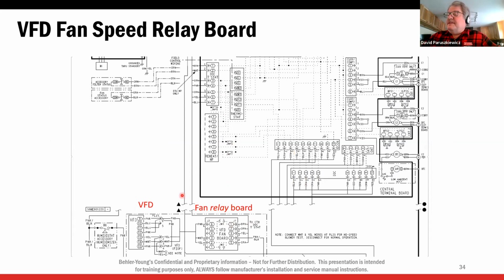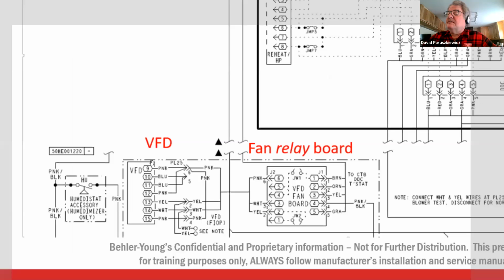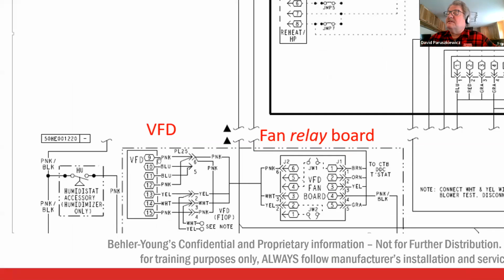Okay, so this is the VFD right over here. This is the terminal board we just looked at, the fan relay board. This is all pretty straightforward. So here's that. Let's zoom in on this thing for a second. Here's that pink wire. So that's 24 volts DC, which goes into the relay board. Now, if high speed calls, that relay sends 24 volt DC back down the white to terminal 14, tells the VFD to turn the blower on.